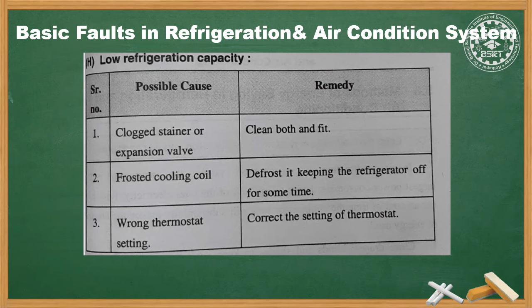Last fault, or last possible fault, is low refrigeration capacity. The possible causes are clogged strainer or expansion valve. Clean both the strainer and expansion valve. Frosted cooling coil. Defrost it. And wrong thermostat setting, set the thermostat to proper setting. So above mentioned are some of the faults and its remedies in refrigeration system.